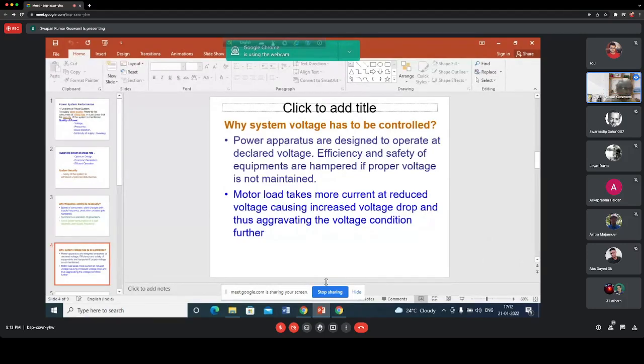If the voltage is below the declared voltage, then obviously there will not be stress, but efficiency will be hampered. So at the declared voltage, the efficiency will be maintained and the expected life of the equipment also can be maintained. This is one of the reasons why voltage has to be kept constant. Another reason is related to the stability of the load. What happens to motor load? You know that most of the loads in any power system are basically motor loads.